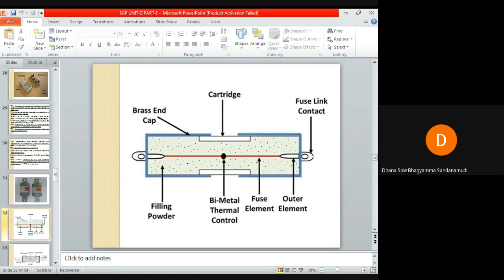So this HRC cartridge fuse consists of a high resisting ceramic body having metal end caps. So these are the metal end caps. Okay, it is made up of a high resisting ceramic body, and inside this ceramic body, the metal end caps are connected to a silver current carrying element. This red line, if you see, is a silver current carrying element. This is nothing but the fusing element. Okay, so the spacing surrounding this silver current carrying element is filled with a filling powder. This filling powder can be chalk powder or plaster of Paris, quartz or marble dust. The purpose of filling this powder in the spacing surrounding the fusing element is that it will quench the arc if an arc is struck between the contacts, and it also acts as the cooling medium.